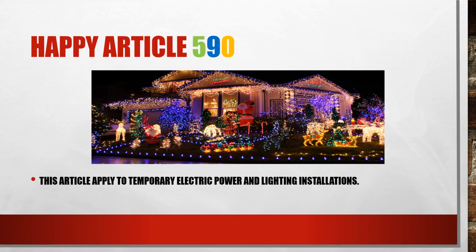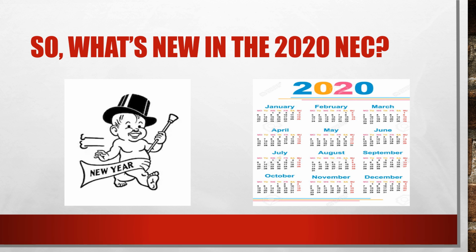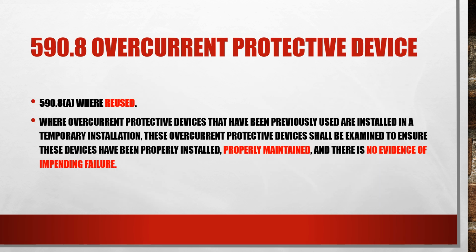Happy Article 590. What is Article 590? It applies to temporary electric power and lighting installations. So, what's new in the 2020 code for Article 590? Well, let's look at some. This new section, 590.8, gives us guidance for overcurrent protection devices. And 590.8(A) talks about where reused. You notice right here, where reused.